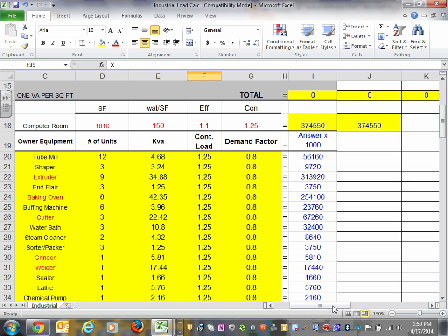Anybody design data centers, guys? Feel free to email me so I can correct it if I'm wrong. That's what I hear from the people that I deal with. So for this project, guys, we allocated our data center in this area, close to 1,800 square feet, a little guy in that room. Yours could be 2,000 to 10,000, 100,000 if you want it. And this is only the area where your racks are. We are allocating 150 volt-amps per square foot based on the servers that we're using. Yours could be different. Then you increase efficiency.